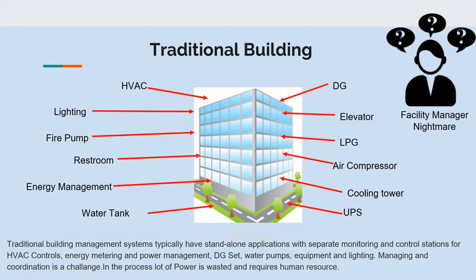Let me take an example of a building where a typical air conditioning consumes almost 60% of your energy consumption. Earlier, before the pandemic, the air conditioning used to start at around 9 a.m. in the morning, with pre-cooling starting at around 8 a.m. at a fixed temperature of 24. Instead of doing that, if they start the air conditioning at 7 a.m. at a temperature of 28 degrees and reduce 1 degree every 30 minutes, that is 7 a.m. 28, 7:30, 27, 8 o'clock, 26, 8:30, 25, 9 a.m. 24. So this small step will have a similar cooling effect, but will give a lot of energy savings.